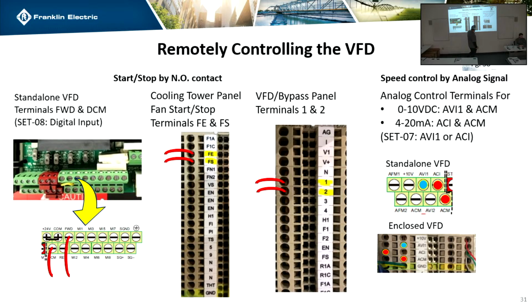And then as I was saying before, here's that plus 10 terminal. All of our panels, it doesn't matter if it's a disconnect, bypass, anything we put together, we are going to wire the VFD's analog controls to terminal blocks just so it's easier for you guys to get to.